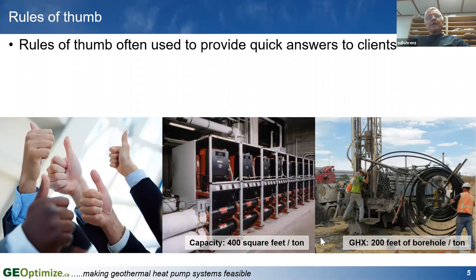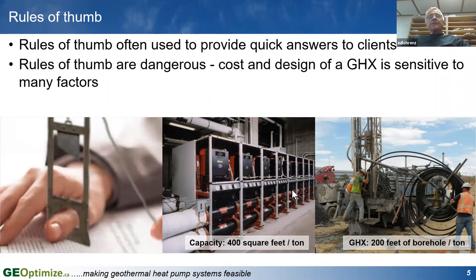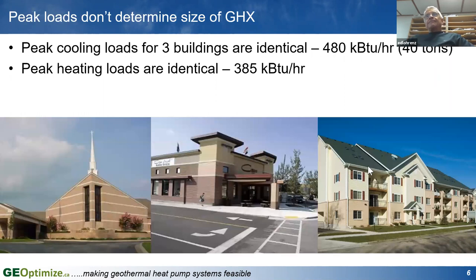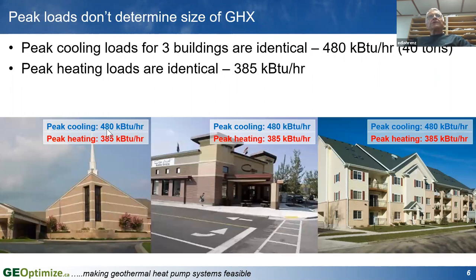And no rules of thumb are available that I know of can really take into account all those different variables. So first rule of thumb, cut off the thumbs. So an example of why the rules of thumb are so misleading. If we've got three buildings, a church, a store, an apartment building, they may have exactly the same peak heating and cooling loads, 480,000 BTUs per hour in cooling, so about 40 tons, and the same identical peak heating requirement, 385,000 BTUs per hour.